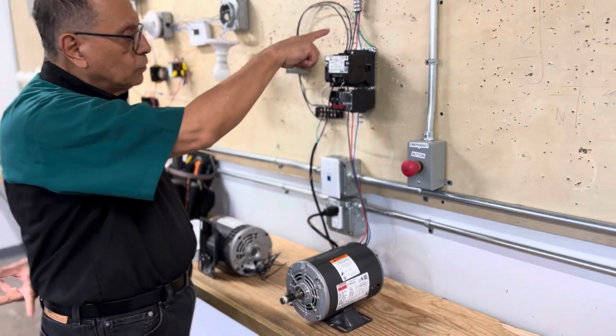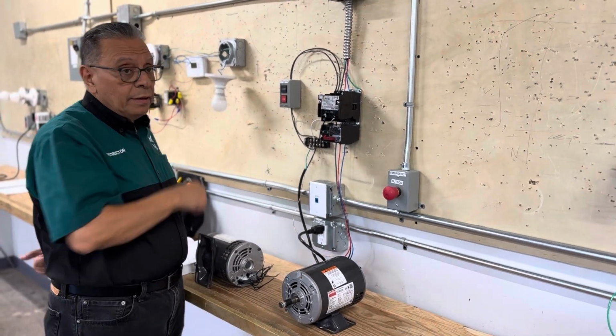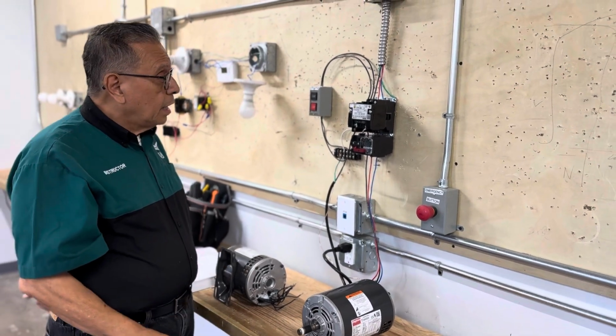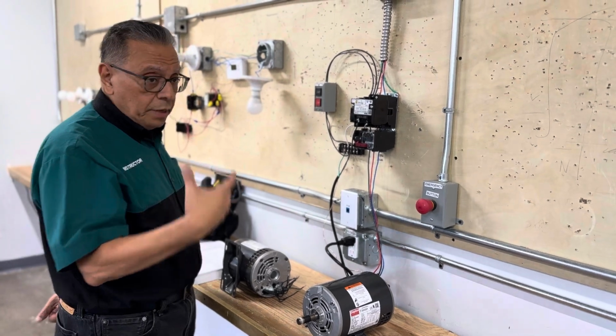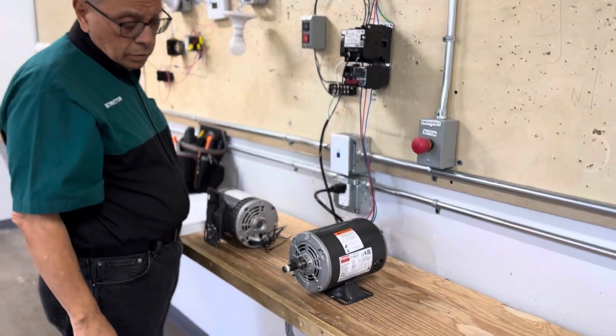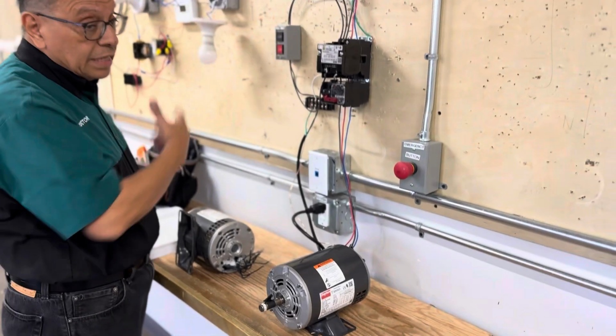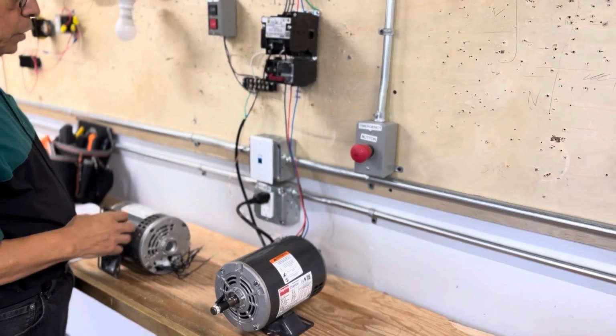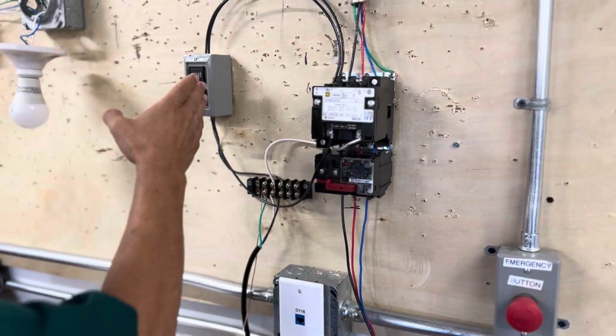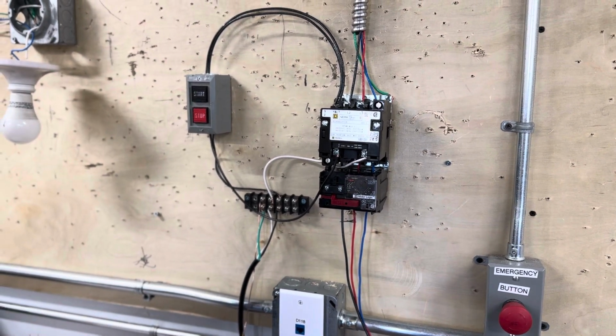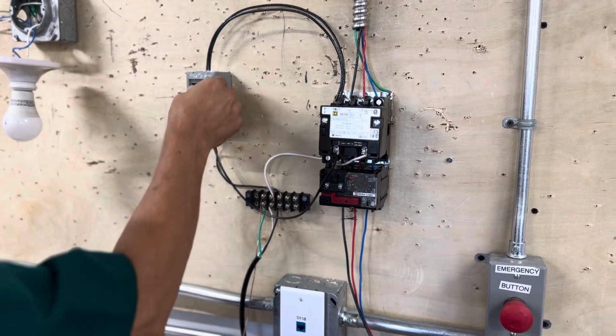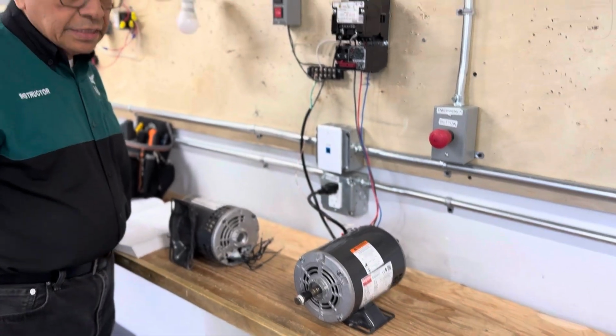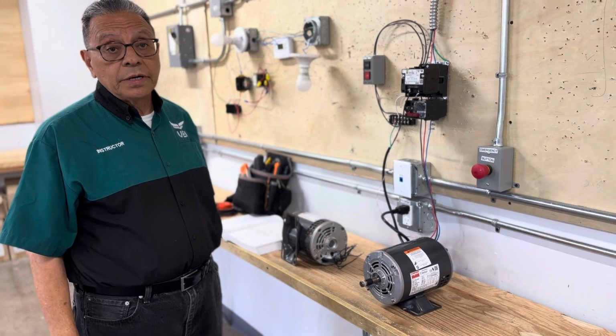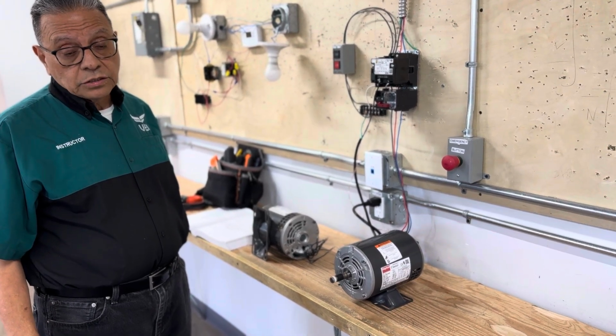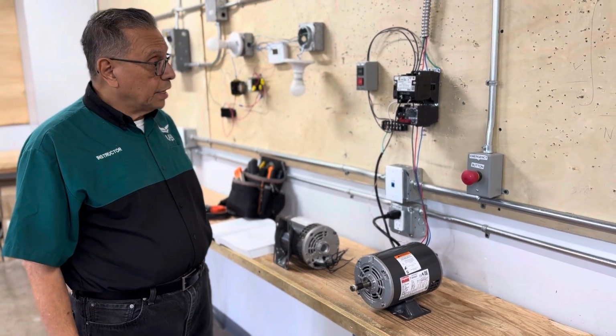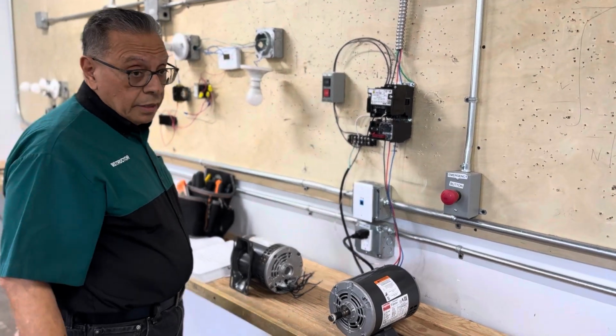The objective is that the student learns how to connect a contactor that will be controlled by a push button station, one push button station. This is manual control; the operator has to come and stop or start the electrical motor. But it's very important that we add some protection between the start and stop, a timer that provides time on delay, minimum 5 minutes, because if we start and stop over and over, the stator of the motor will be overheated, and as a consequence we will eventually have a short circuit on the stator. So we need to include a time on delay timer.